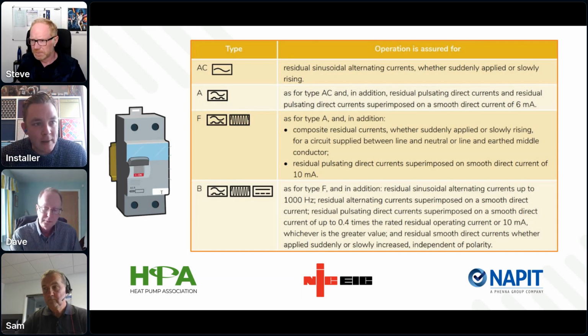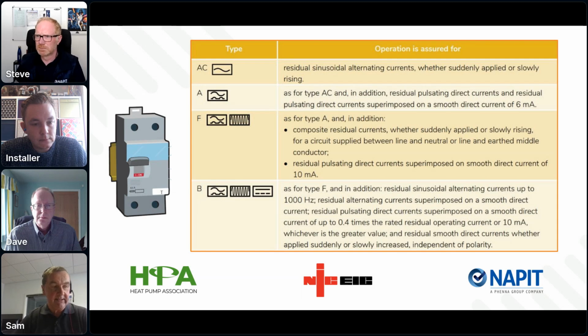And Sam, why is it categorically stated that type AC can't be used? So again, our British standard for the electrical installation has a regulation which clearly states that type AC RCDs shall only be used to serve fixed equipment where it is known that the load current contains no DC components. As Steve said, because of the equipment within the heat pump, particularly things like inverter drives, but generally any electronic controls, that will introduce a DC element into the installation. So we definitely can't say that it's known that no DC component will be produced. That means ACs definitely can't be used unless, and I don't think it would be possible, you got a statement from your heat pump manufacturer to state that there would be no DC components produced by the item of equipment.